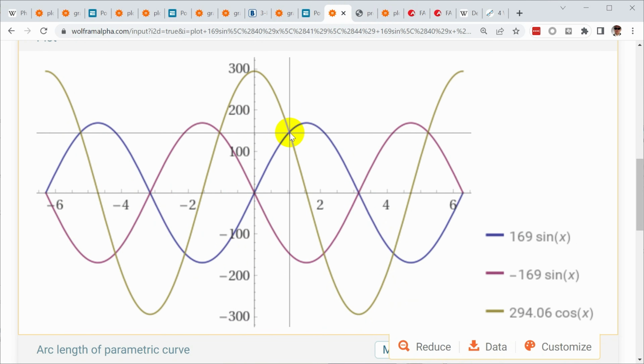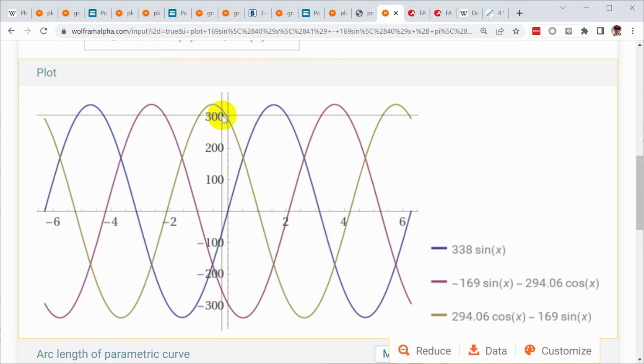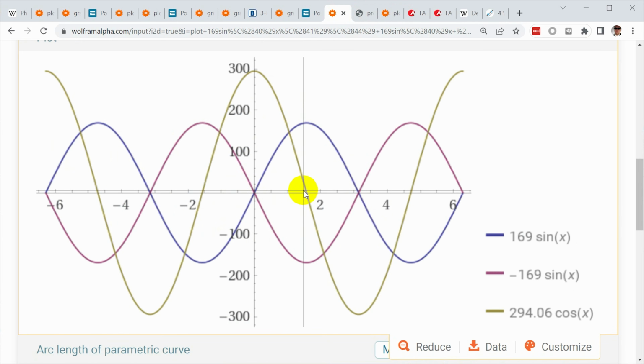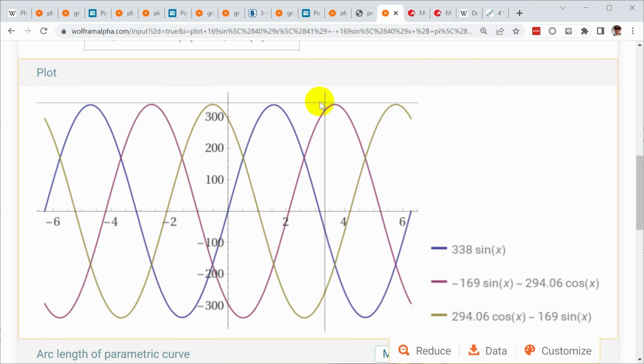Well, what about out here where they cross? Yellow minus blue, if they're the same amplitude, well, then that point should be at 0. And so right at that point, the yellow line here is crossing 0, halfway between 1 and 2 on the graph. Halfway between 1 and 2 on the graph is where they cross. So as non-intuitive as it seems, if you actually take the difference between these crazy waveforms being generated by the rotary phase converter, you get nice, neat three-phase power.